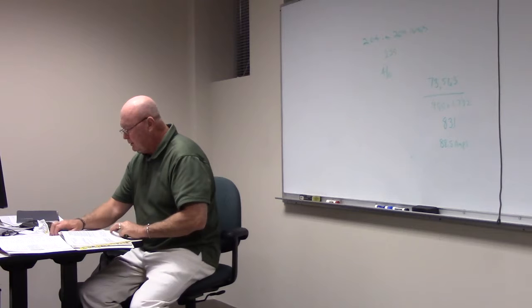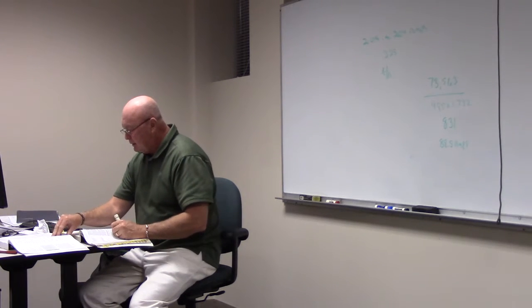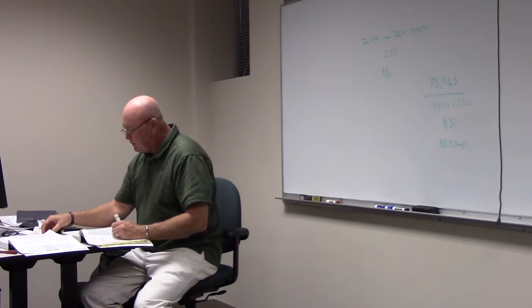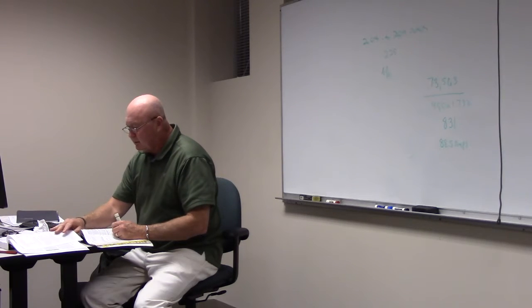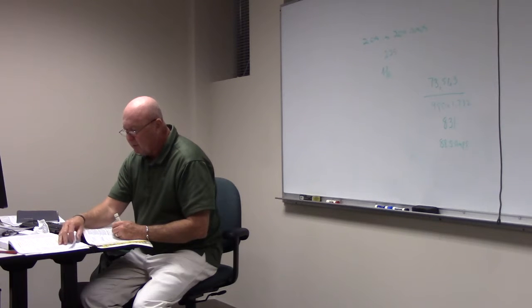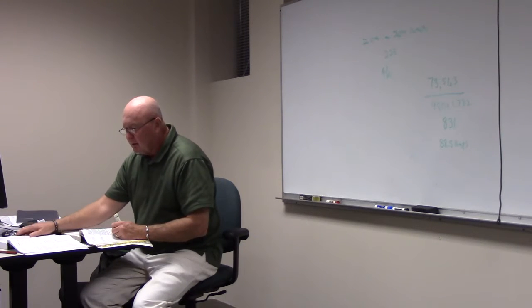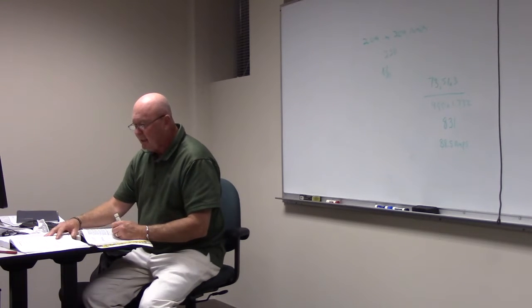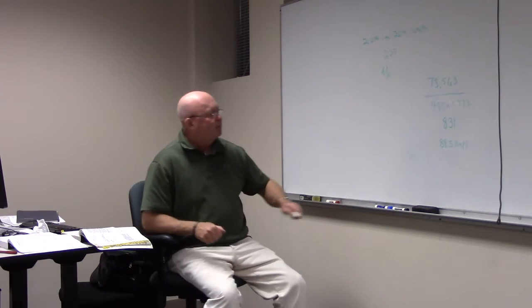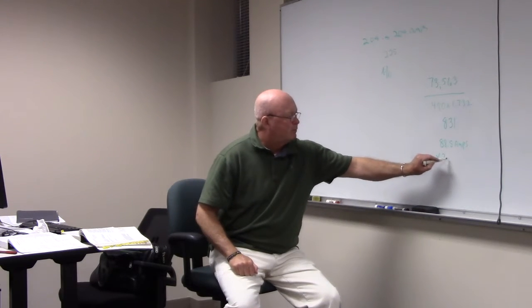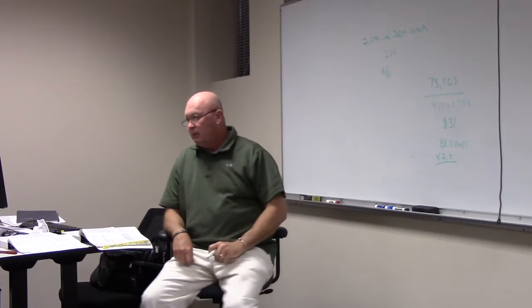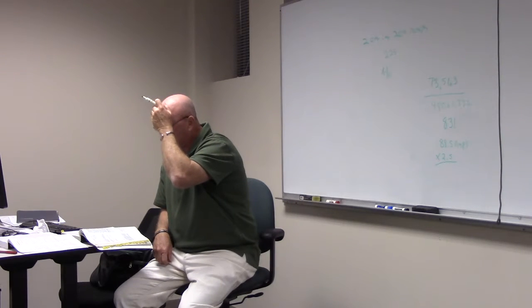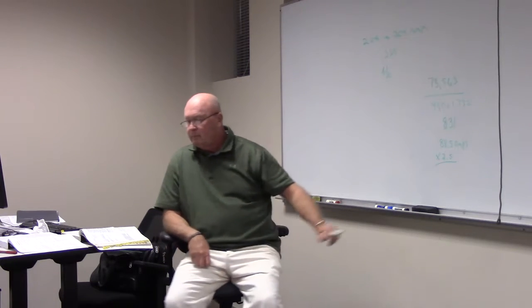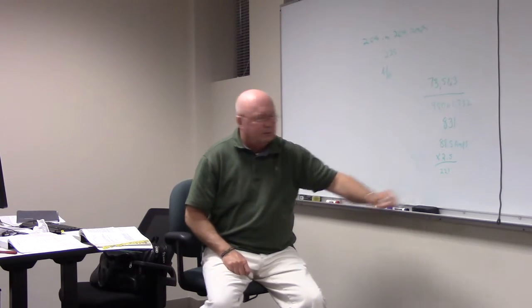So we look there. Step 11 says NEC 450.3, because the secondary protective device is used, the maximum setting of the transformer overcurrent device shall be 250%. So we're going to take that 88.5 and multiply it times 2.5. 88.5 times 2.5 is 221. If you look there in the book, that's what it comes up with.